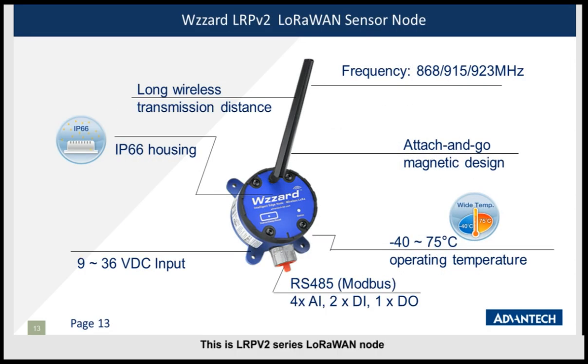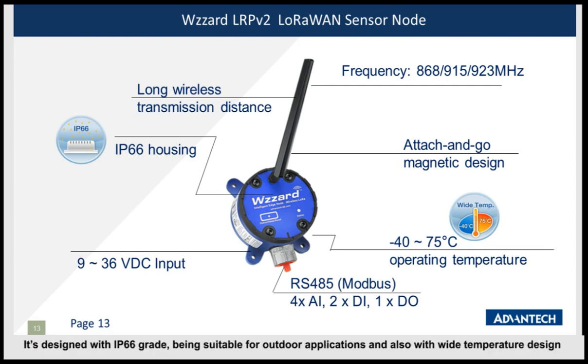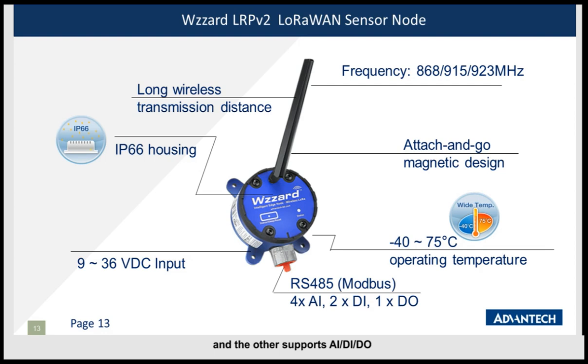This is the LRPv2 series LoRaWAN node. It is designed with IP66-grade protection, suitable for outdoor applications, and features a wide-temperature design. We have two kinds of node series: one supports Modbus RS485, and the other supports analog input, digital input, and digital output. It also supports three frequency options: 868 MHz, 915 MHz, and 923 MHz.